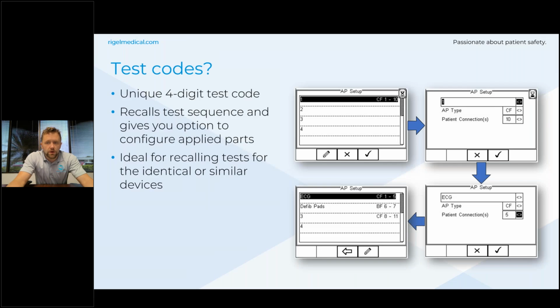So test codes, what are they? Less relevant to the US market, but we can have 4-digit test codes which allow you to input the types of applied parts. Now this applies to IEC 60601 and less so to NFPA 99. The reason for that is that NFPA 99 groups the applied parts together, and also there are no classifications in NFPA 99. You will see on the AP setup here that there's CF, BF, and CF again.